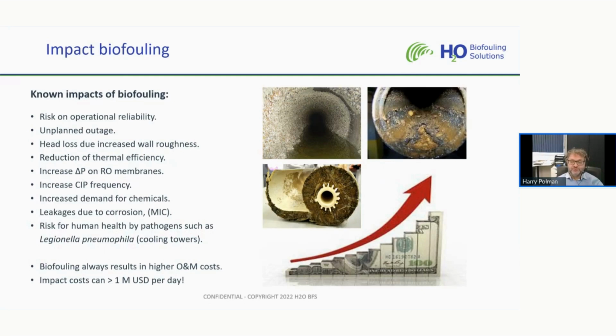Biofouling has a big risk on operational reliability of the utility. It also reduces the thermal efficiency of the plant. It can increase the differential pressure on RO membranes as you get fouling on membranes. Biofouling always results in the need for more chemicals to clean it and to control the amount of biofouling in your system. And in cooling towers, biofouling can also result in a health risk for humans caused by the Legionella bacteria, which can grow and multiply when a biofilm exists in a cooling tower. Biofouling always results in higher operation and maintenance cost, and the impact can easily be more than $1 million per day.